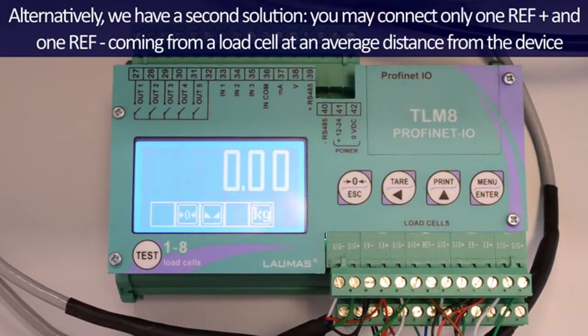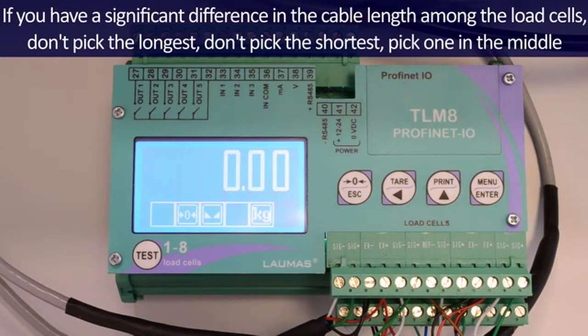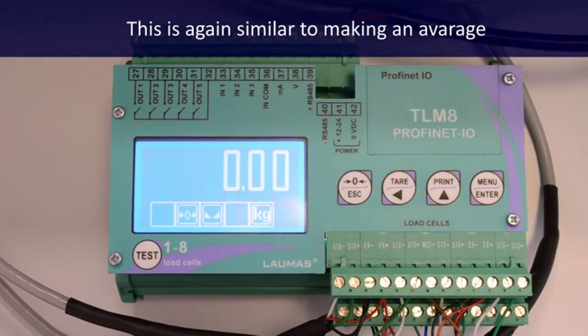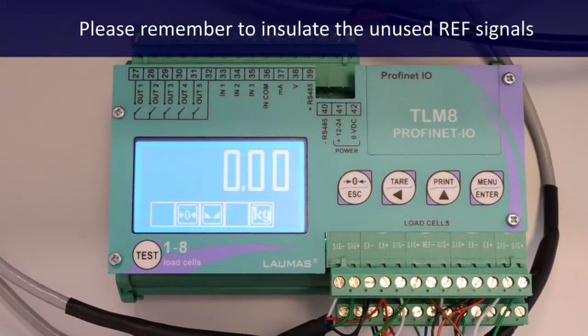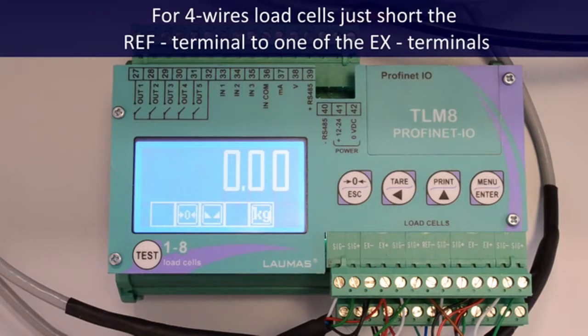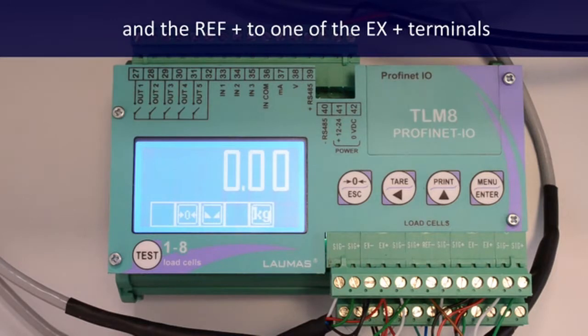Alternately, we have a second solution. You may connect only one ref plus and one ref minus, coming from a load cell at an average distance from the device. If you have a significant difference in the cable length among the load cells, don't pick the longest, don't pick the shortest, pick one in the middle. This is again similar to making an average. Please remember to insulate the unused ref signals. For 4-wire load cells, just short the ref minus terminal to one of the excitation minus terminals, and the ref plus to one of the excitation plus terminals.